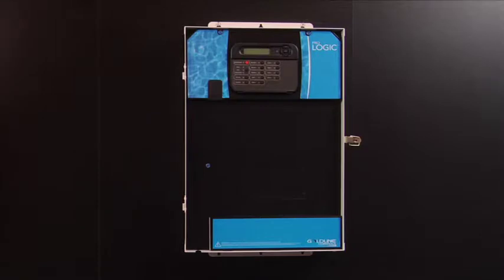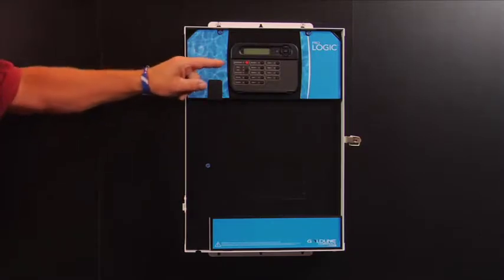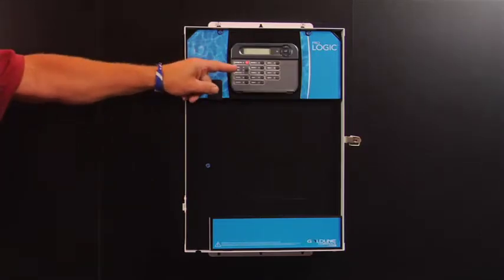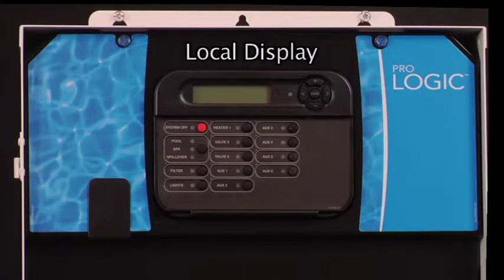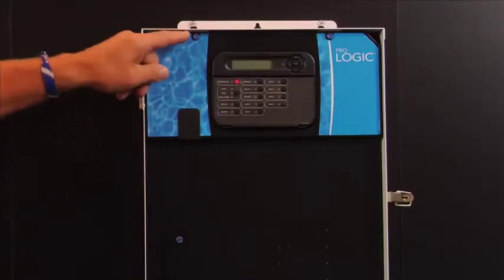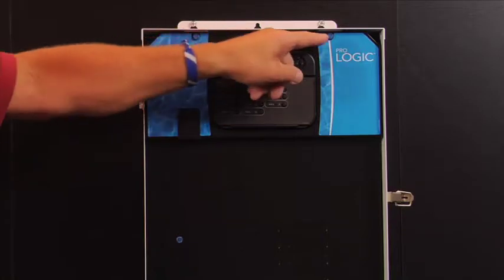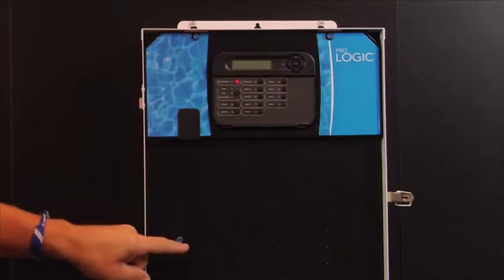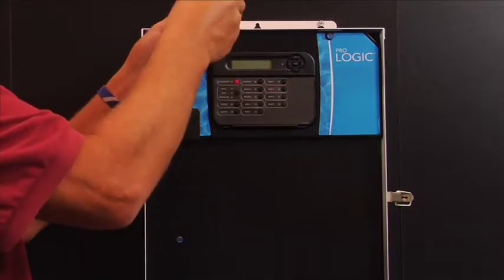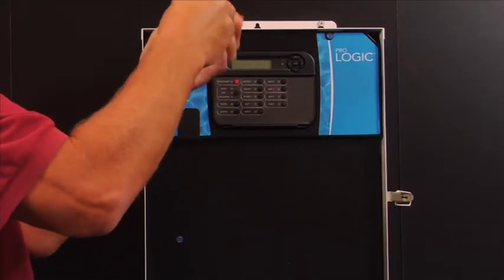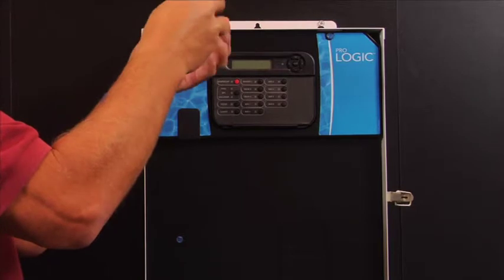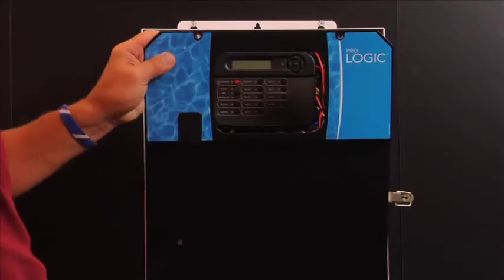Taking a look at the control box, the first component you will notice is the local display. This allows you to program and operate the ProLogic. It will also display messages and system status. The other key components of the control box can be viewed by removing the 3 hex head screws that retain the front panel. Use a 5/16" hex-headed driver to remove the 3 screws. Remove the front panel.